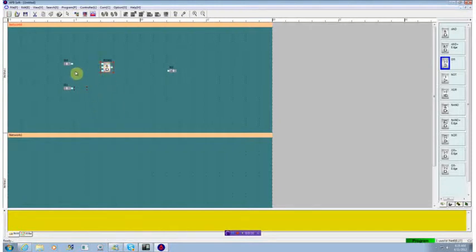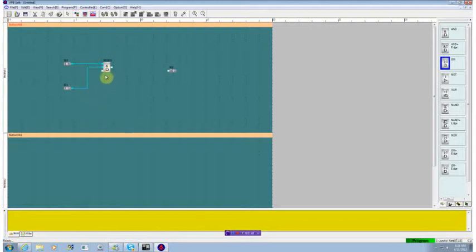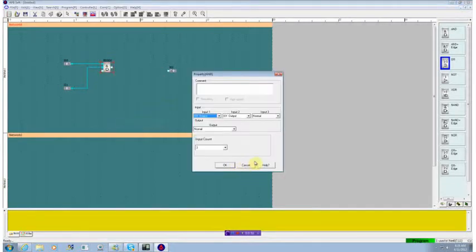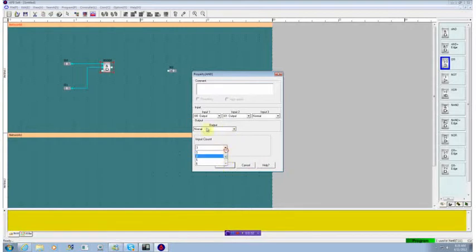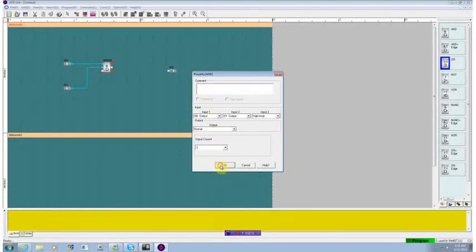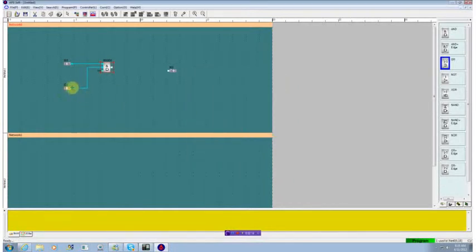For the AND gate, we will connect one of the inputs to this point here. We'll connect this input to that input. We see that we have an unused input on our AND gate. So we click on the box, open up the property. We see that the input count can range from three up to eight. Each AND gate can have up to eight inputs. A minimum is three. We're not using three inputs. So we need to set that to a default value. For the AND gate, we'd set that high. So it's always going to be on. And we won't bother giving this a name. Let's just leave it as an AND gate.